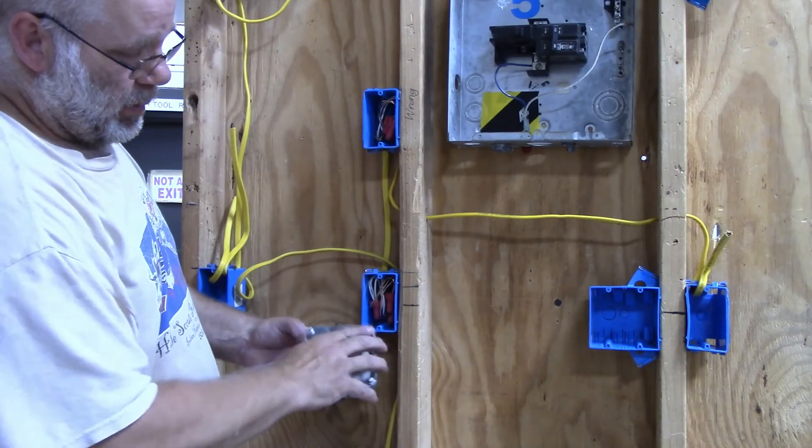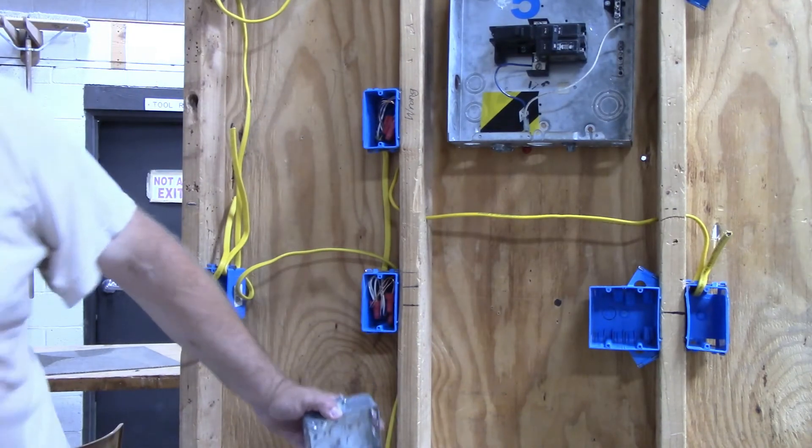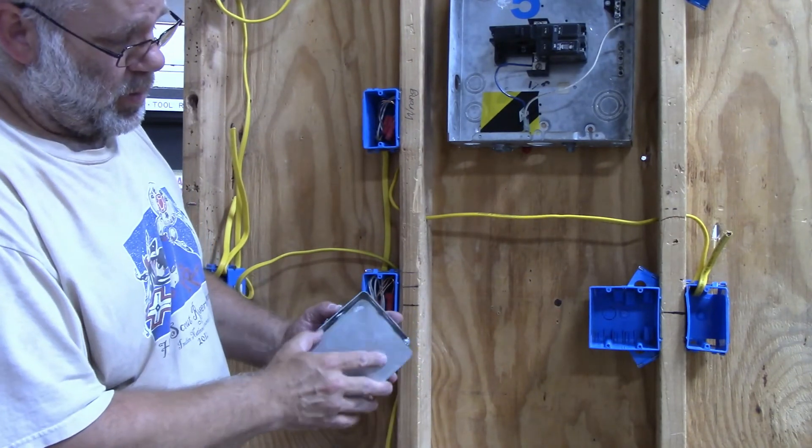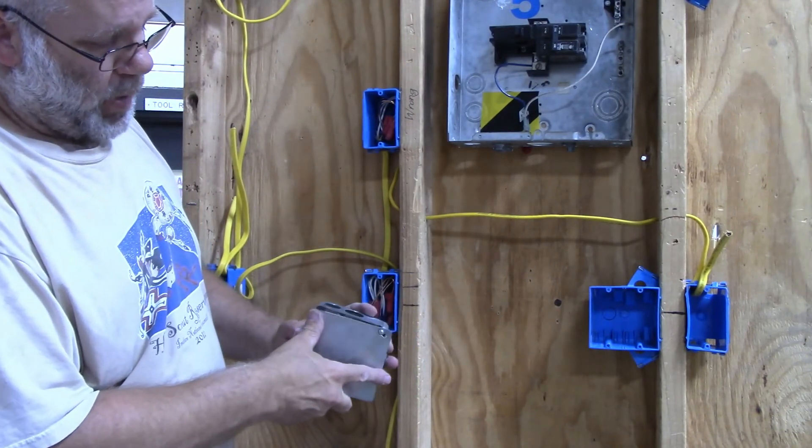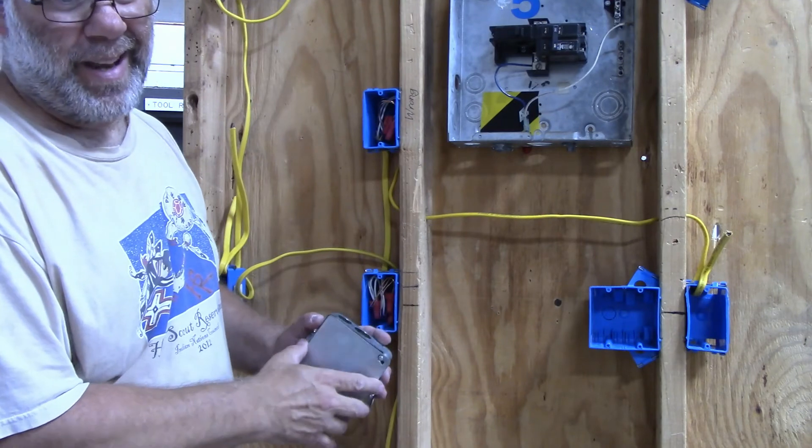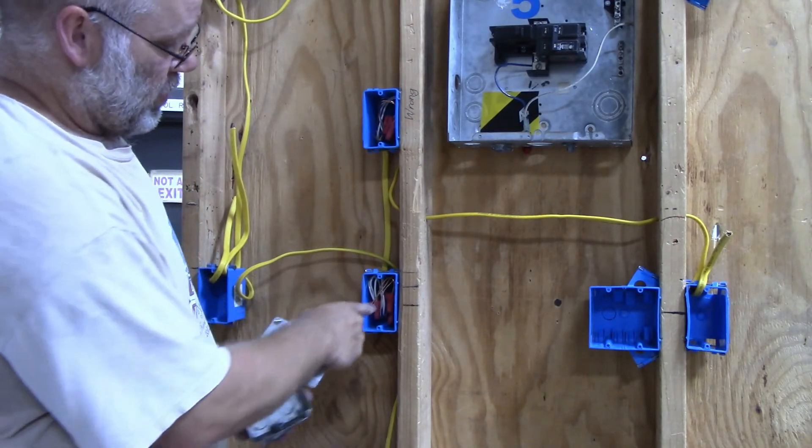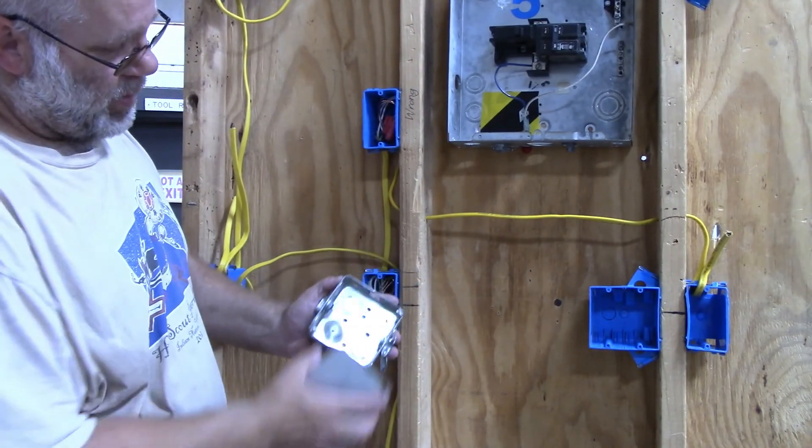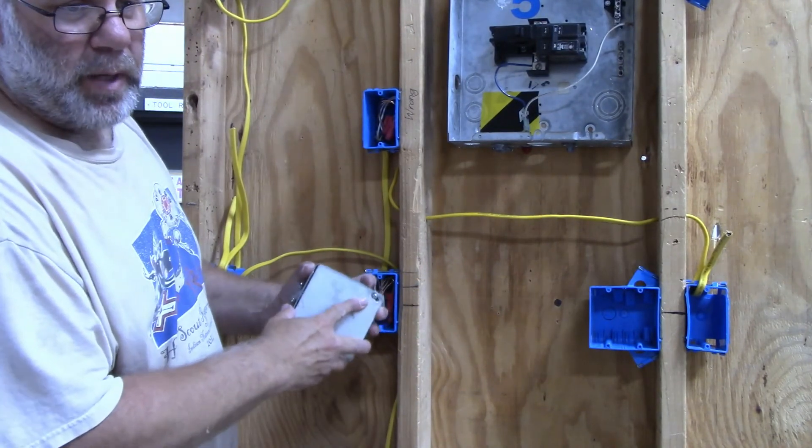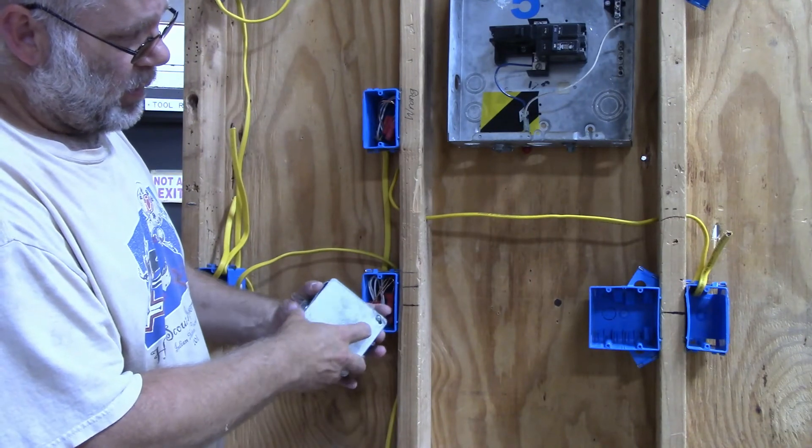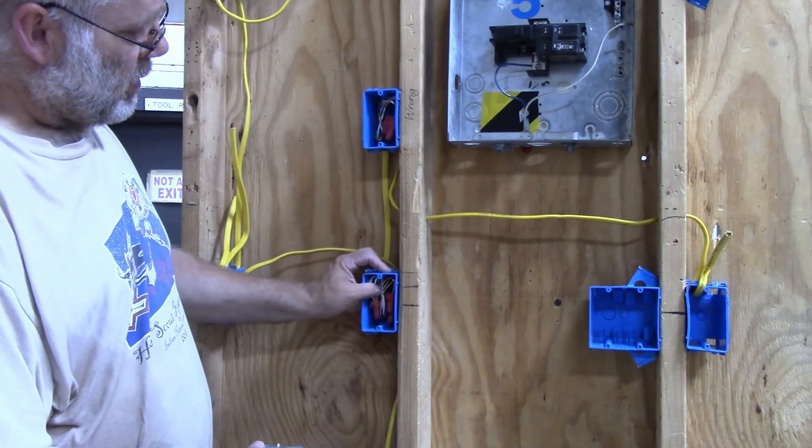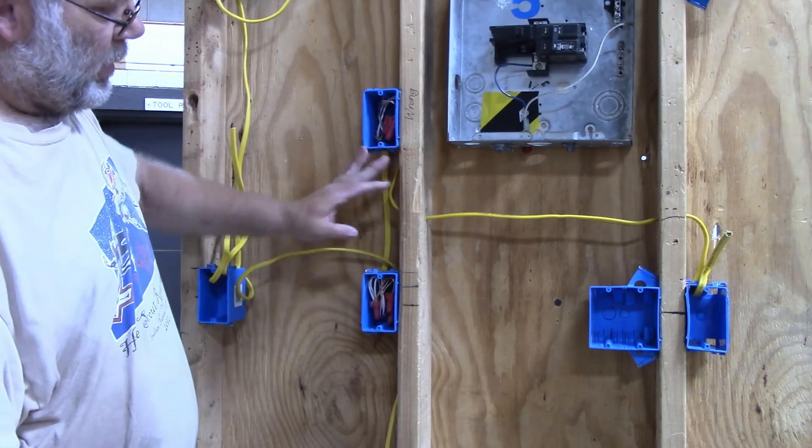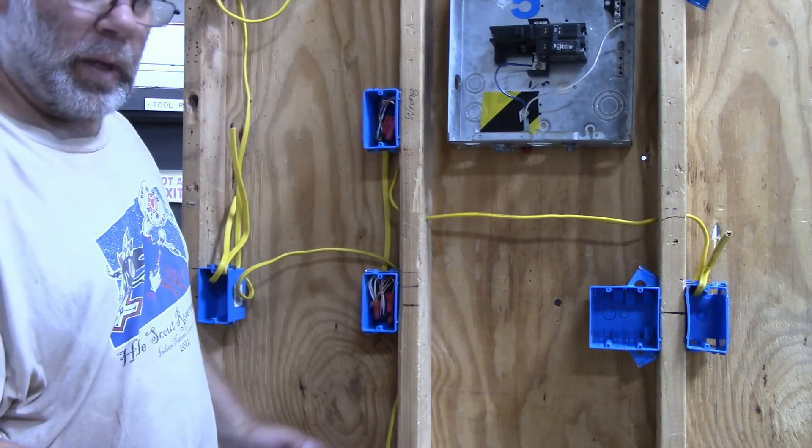And then of course, make sure you cover them up with a blank cover so you do not have any wires exposed. You cannot have any connections exposed. So if there's a wire nut on anything, it has to be covered up. So if I have wires in this box, then it has to be covered up. So this is how you would splice into an existing line to add a new outlet.